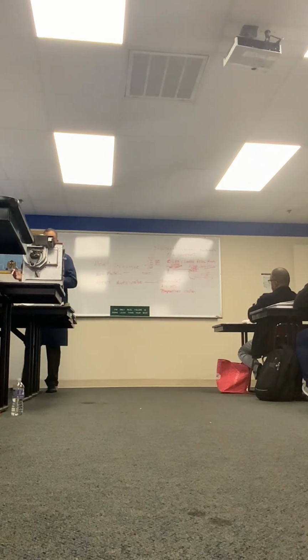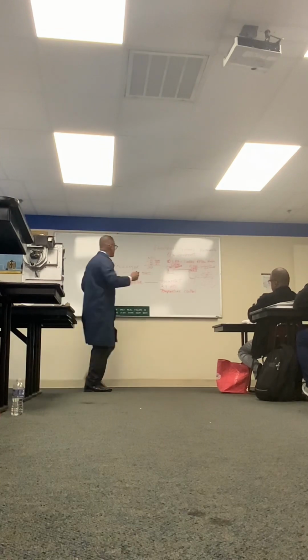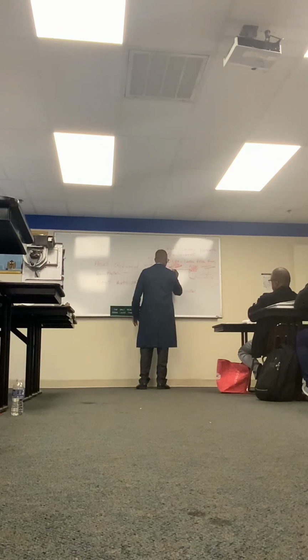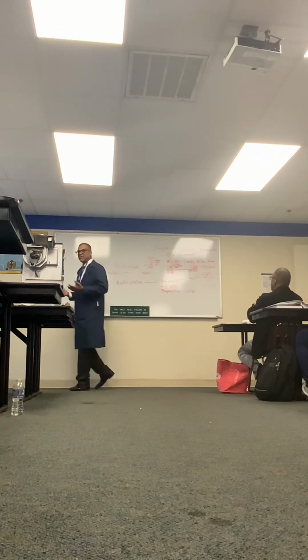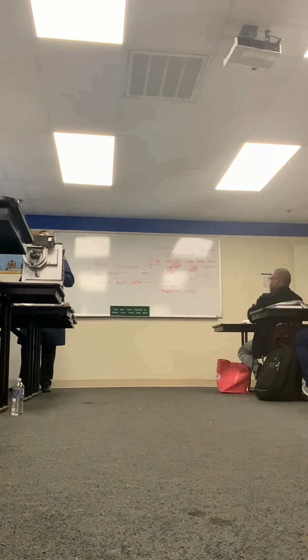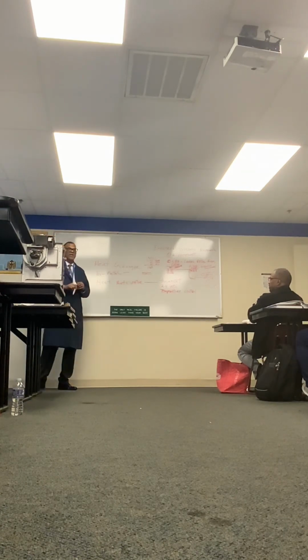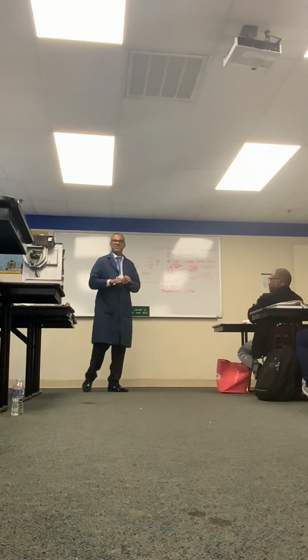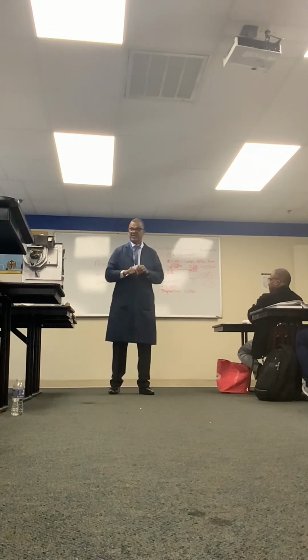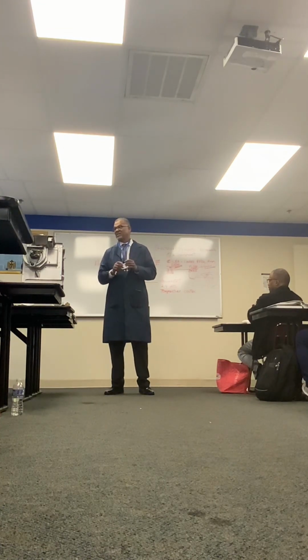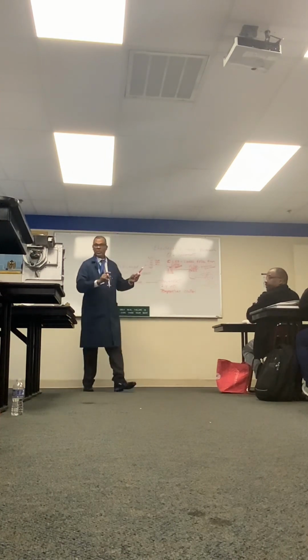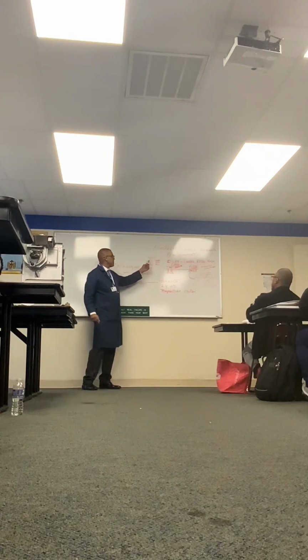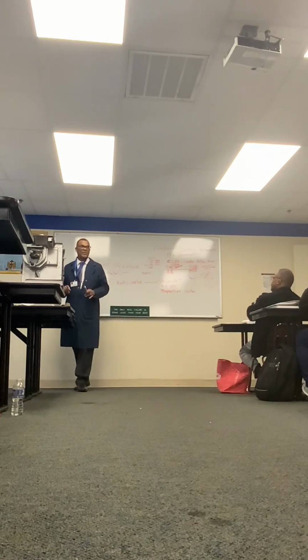So that's why you can't say, oh, there's some empty circuit breakers here, I'll just use one of these. Well, what kind of amperage are you looking for? It might not be that much left. You might have to have another service pulled in order to continue that service. And a lot of houses are still 100, 150, 200 amps. I don't know what mine is, I think it's 300. That's the whole house.